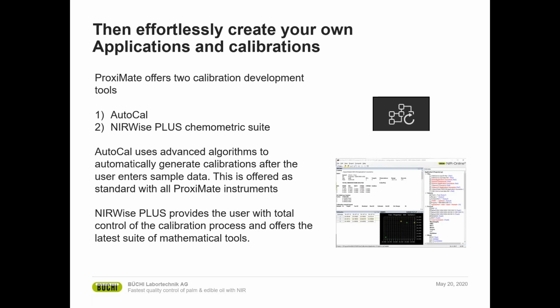Now, you might have read a little bit more, may have developed your own expertise of NIR application building, and you may wish to take that further. It's possible to do that with the NIRWise Plus chemometrics suite. That can be used on a laptop or can be installed on the ProxiMate instrument, and that allows you to take data easily from the ProxiMate instrument and to develop your own applications and calibrations on maybe a laptop in your own office, and then import those into the ProxiMate instrument in the production area. So you can see there's full flexibility with these software tools and with the hardware options that are available.